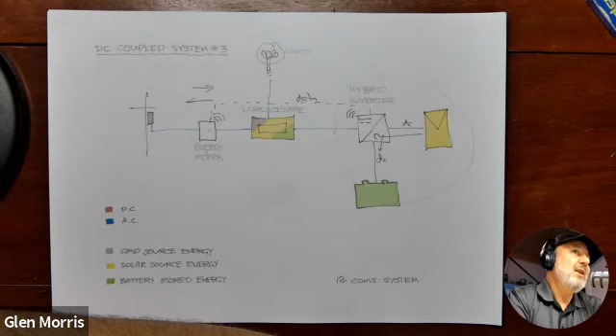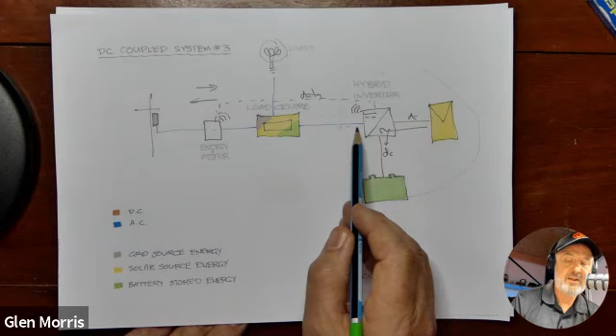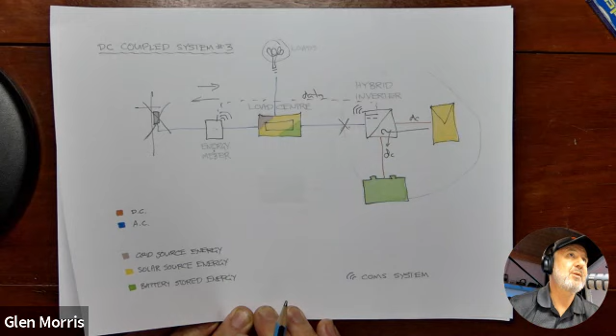So this is a slightly different version. Let me bring that drawing back again. You'll notice this one shows we only have a single connection to a load center. What will happen is if the grid fails here, we actually have to turn off that inverter. It can't support the loads when the grid fails. So in this design, there is no backup power available.